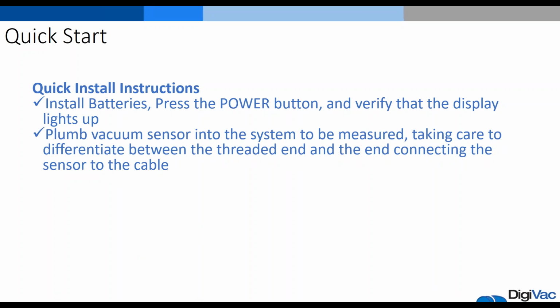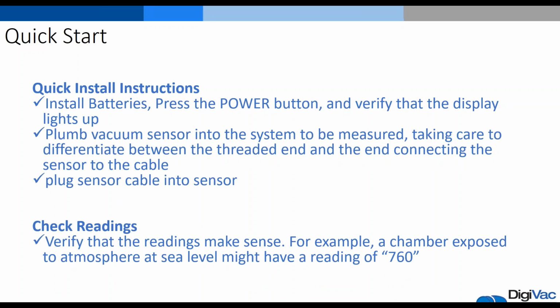You would plumb the vacuum sensor into your vacuum system, and then you would plug the sensor cable into the sensor, and you would verify that the readings make sense and are accurate. So you would make sure it's reading accurately within the system that you're plugging into. So if it's reading atmosphere at sea level, you would look for a reading of 600 to 760 torr, which would be normal for that environment.